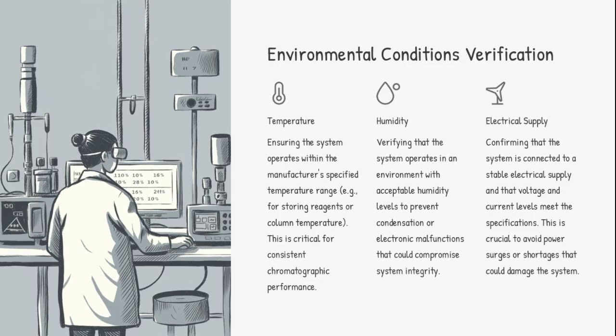Environmental conditions verification ensures the system operates within the specified temperature, humidity, and electrical supply parameters. Temperature control is critical for consistent chromatographic performance. Humidity levels must be acceptable to prevent condensation or electronic malfunctions. Electrical supply must be stable to avoid power surges or shortages that could compromise system integrity.